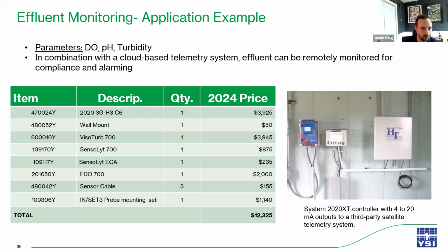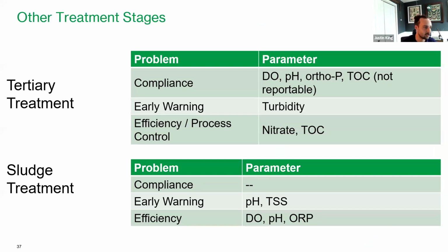And then I believe we've got one more slide just to quickly touch on tertiary treatment and sludge level treatment. So these are some additional treatment stages where instrumentation can be used in tertiary treatment, which is usually an additional stage of clarifying water that's going to be used in a reuse application. It requires a lot of monitoring to achieve a high quality water product that can be used for reuse applications. So we typically see DO, pH, orthophosphate, TOC, and turbidity monitored here, and they are all used in some way, shape, or form for compliance monitoring and process control.